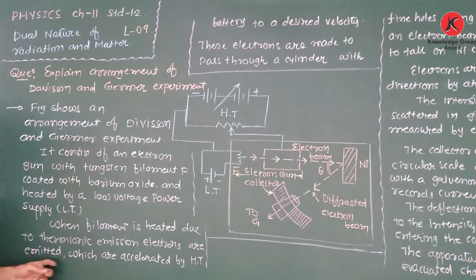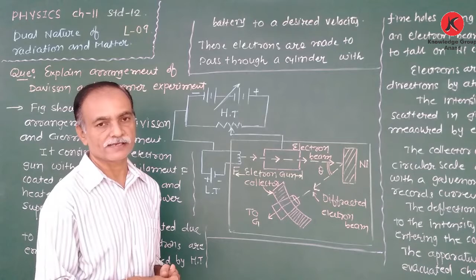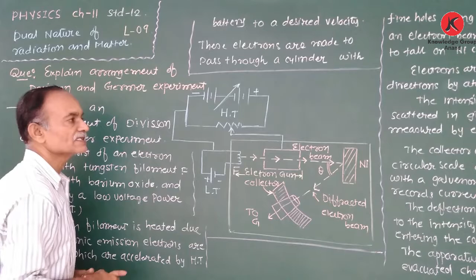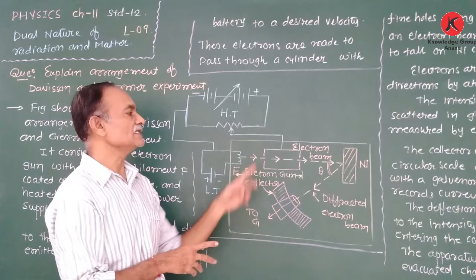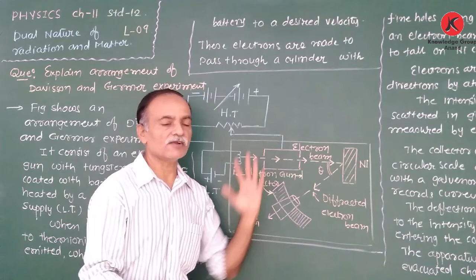As the low tension battery is switched on, current passes through the filament, and as a result, the filament gets heated, and due to thermionic emission, the electrons are emitted, which are accelerated by the high tension battery. All the electrons emitted by the filament are attracted by the cylinder. This cylinder is connected with the high tension battery, that means high voltage is applied to this cylinder to reach the desired velocity, and as a result, the emitted electrons are converted into a beam, and its velocity we can fix.